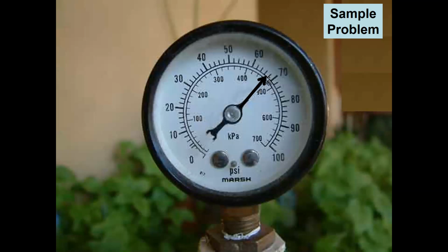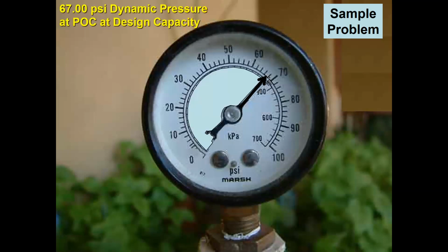So here's a pressure gauge. Does everybody know how to read a pressure gauge? Has everybody seen it before? So we know what our pressure was. If we hook this pressure gauge up to our main, we should have been at 80 PSI. However, we're at 67 PSI. So 67 PSI is what our dynamic pressure was at our point of connection. As soon as we plugged our pipe in, that's what we knew we were starting with to design our system or build our system out from. So we have 67 PSI to work with.